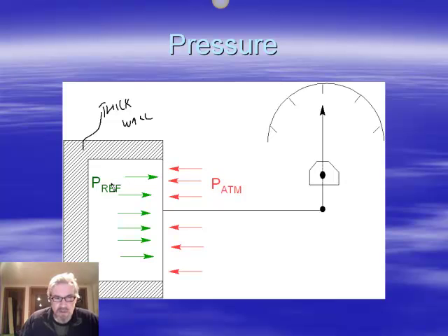And then you seal inside there a gas at what we call a reference pressure, a pressure that you know, like 1 atmosphere, let's say, for example, or it could be something less. And then once you know that pressure is right, you weld onto it a thin, flexible diaphragm. This is thin and flexible, sort of like aluminum foil or something like that, so it can flex back and forth. The metal can stretch because it's not too rigid. So what you're looking at is a cross section. If you slice this can in half and looked at the sliced open part, this is what you'd see.